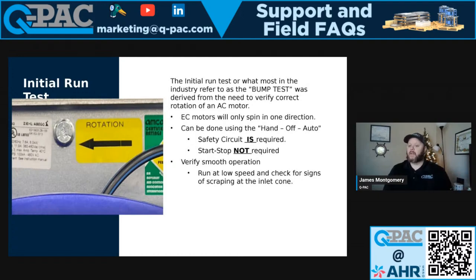Once you've got that, and you've done your verification, making sure your dampers are aligned and all your ductwork is intact, or even if it's not and you're going to run it in some kind of safe manner just to make sure everything runs, then you're going to need a jumper on that safety circuit. The start/stop is the next one. It's not needed for just this hand mode test. When we move on to an auto test, you're going to need the start/stop to be made, similar to the safety circuit. And then you're going to start looking at whether the BAS is going to control this and how they're going to do that.